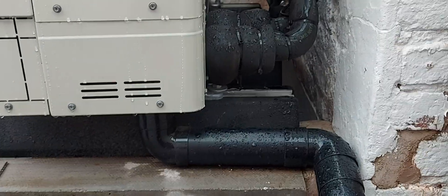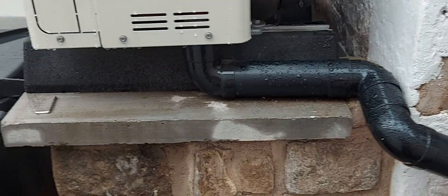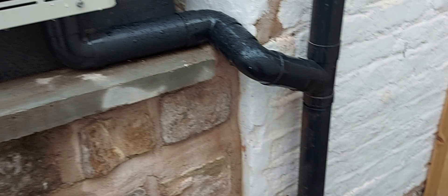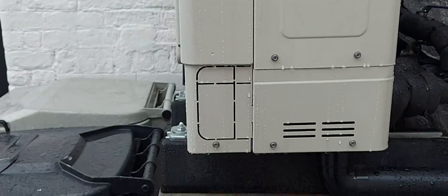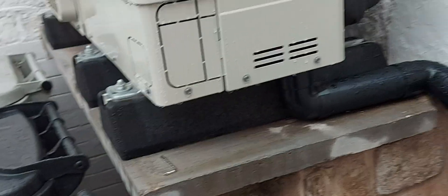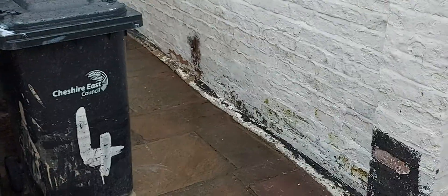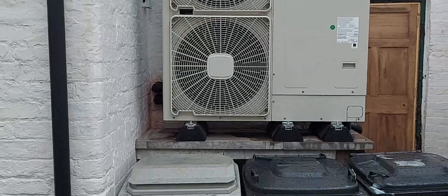Lagged primary pipe — the circuit's got the correct amount of glycol on the primary side. We tapped the condensate drainage into the rainwater there; this is just clear distilled water that comes out of air, not like boilers which are contaminated, so it could just run where the downspout went. We actually built this plinth and raised the heat pump up so there could be bin access — otherwise the bins would have been in front of the heat pump and blocking airflow.